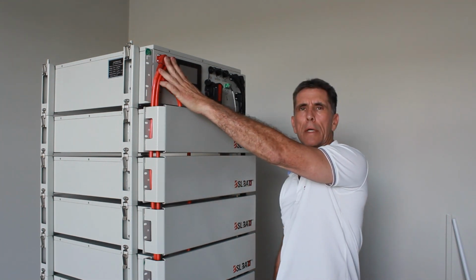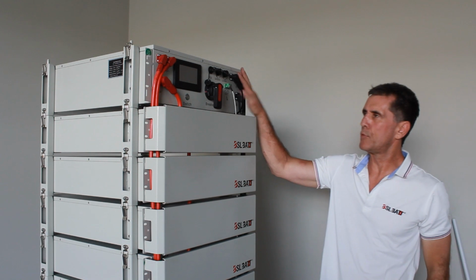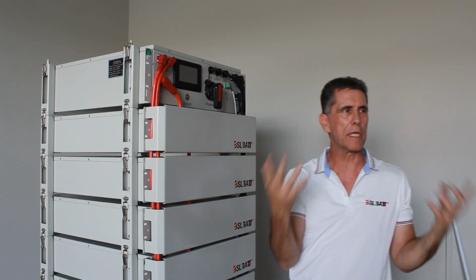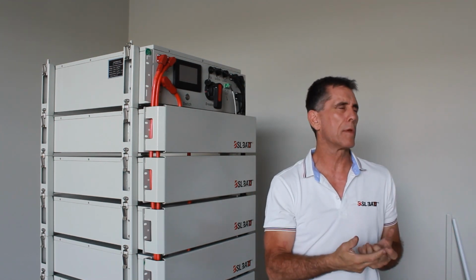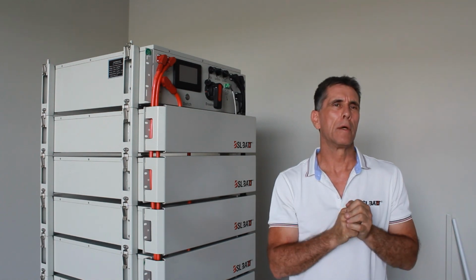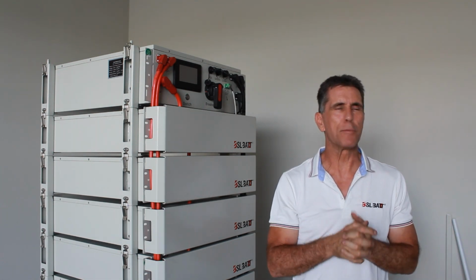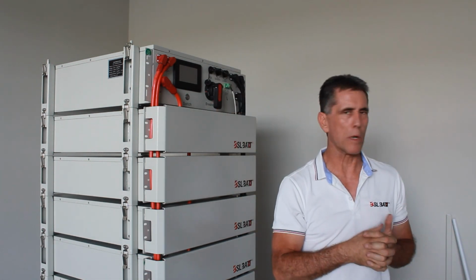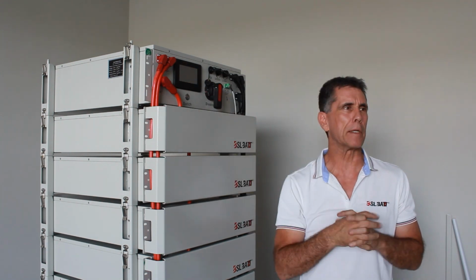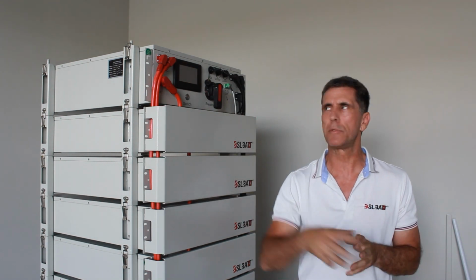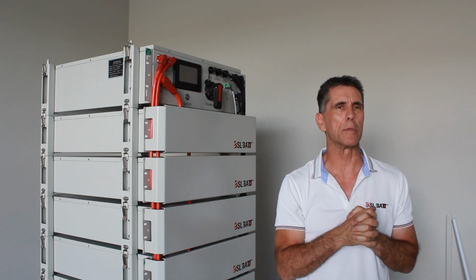My 2 connection cables are already connected, 2 for positive, 2 for negative. For a set-up, you do not have to use both. You can use one, and you'll get a maximum of 100 amps per connection point. It's a 1C battery, but you have 100 amps per connection. If you need more than 100 amps, we advise you to use both cables.